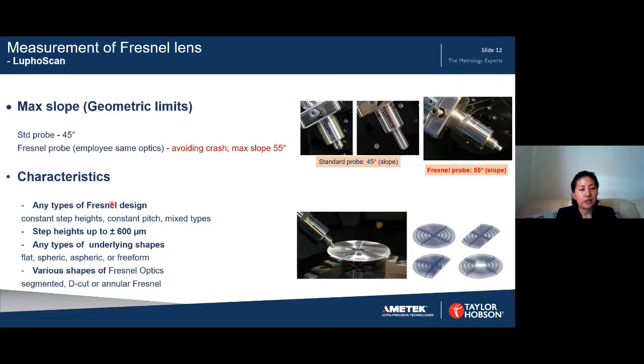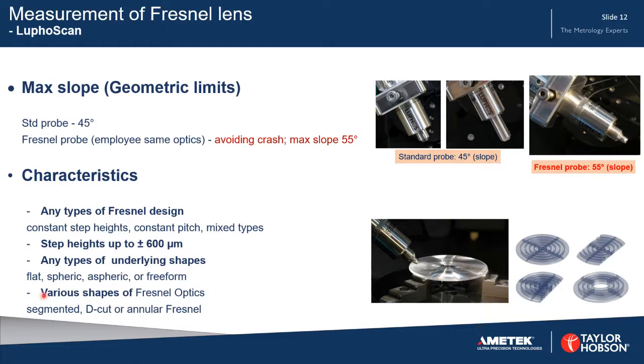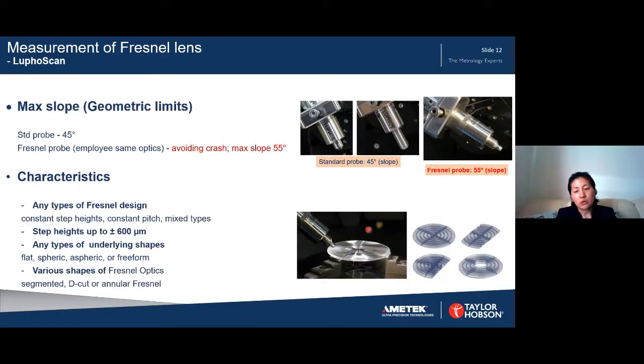With Luphoscan, we can measure any type of Fresnel design — all three different types: constant step height, constant pitch, and the mixed type. Because it has a very large absolute measurement range, it can measure step heights up to plus or minus 600 micrometers. For typical Fresnel lenses the underlying surface is flat, but some Fresnel lenses may have a spherical, aspherical, or even freeform underlying surface — for all these different shapes, Luphoscan has no problems. It can also measure segmented Fresnel or annular Fresnel lenses.